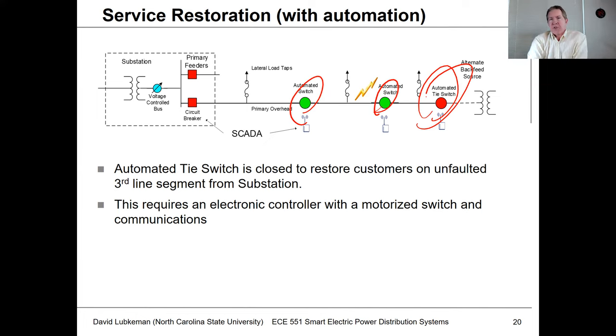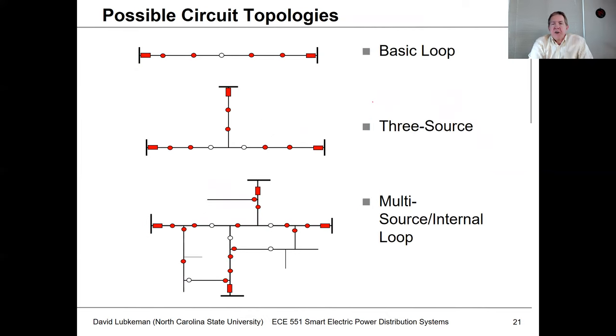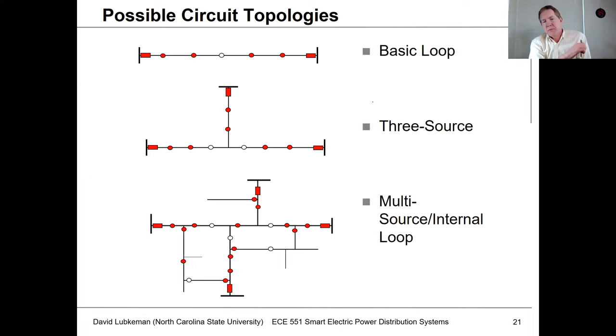These automated switches are designed for this purpose — they wouldn't have the ability to break fault current, but once the fault has been cleared at the substation, they can operate and would typically be able to break a load current. What you need is a motorized switch and a controller. As far as topologies, what I've been showing is what we call basic loops — just one single backfeed — and probably most systems are like this, what we call loop control type systems.